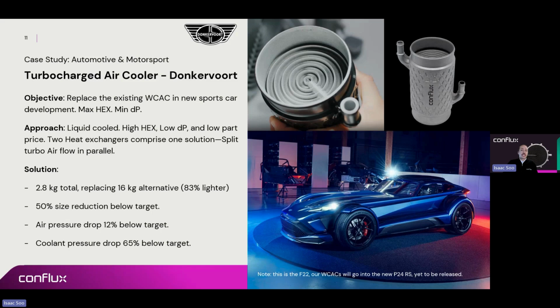So we approached this in an interesting way. We actually were able to split the airflow into two streams, where we put 2 parallel heat exchangers into each stream, which helped us slow down the fluid and really squeeze out the most heat exchange we could out of the air.